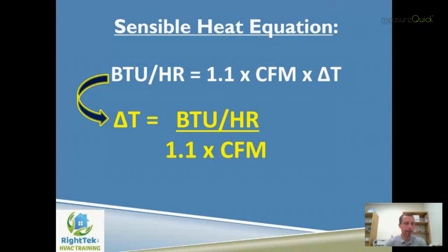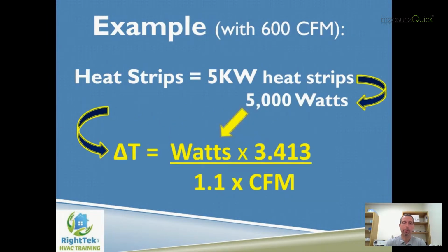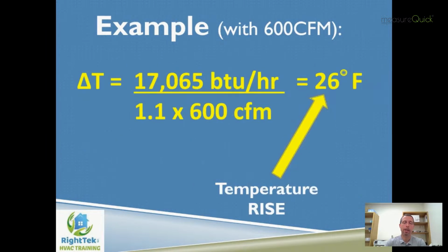And I'm not sure quite where I got cut off, but talking about size and heat strips. And again, Manual S gives us a pretty broad amount of leeway on heat strips, anything from about 95% of our target load all the way to 175%, which to me is pretty extreme. So I like to look at maybe the sensible heat equation, and I'm just going to, again, to catch us back up, accelerate through this. I can do a little bit of basic math, and I can figure out approximately at my nominal airflow, whatever the size of that system is, what my temperature rise is going to look like, on paper at least. So this way I kind of have an idea what's the smallest heat strip I could put in here, save them energy if I'm even using heat strips.